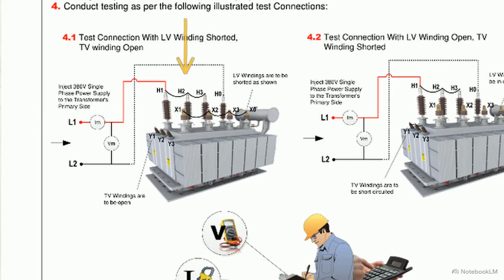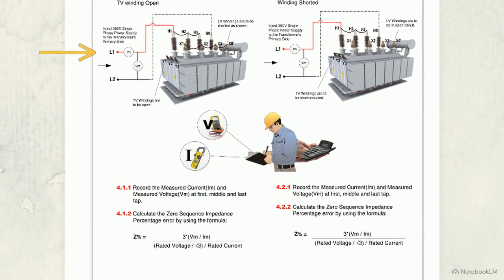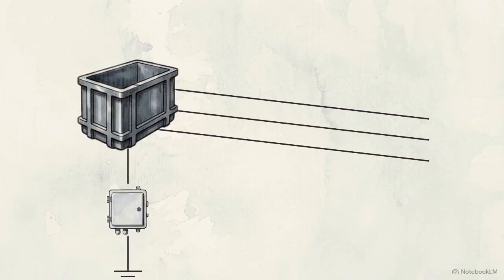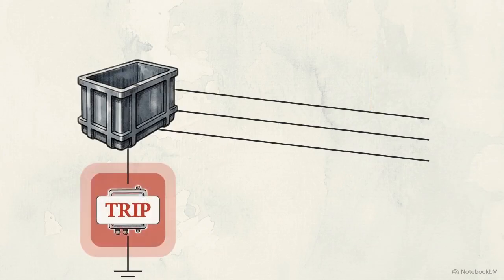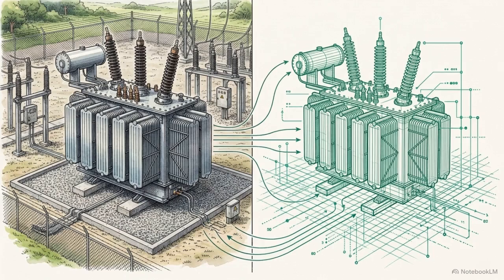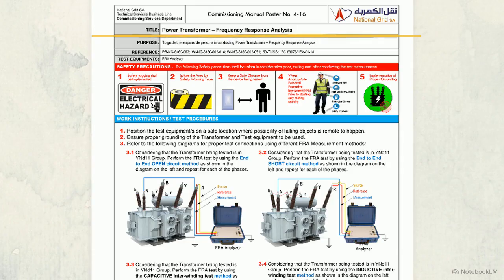Here, the phase terminals are linked together, and a single phase voltage is injected against the neutral to calculate the zero-sequence percentage. This exact value is critical for system planners. It directly dictates the earth fault coordination and determines how the neutral grounding protection will behave during a line-to-ground short circuit. By empirically determining these impedance values, we ensure the actual hardware behaves exactly as predicted by the utility network's digital fault flow models. This schematic references frequency response analysis.